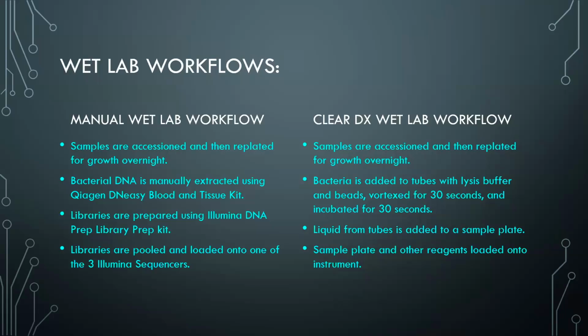The ClearDX workflow is much easier. We accession and replate overnight, just like for the manual. But then all we have to do is add bacteria to tubes with lysis buffer and beads, vortex for 30 seconds, and leave it to incubate for 30 seconds. Take the liquid from the tubes, add it to a sample plate, and then load the sample plate and any other reagents onto the instrument, and it does the rest.